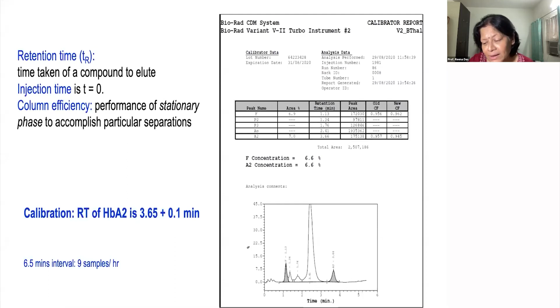After the calibrator has passed through, we have to use two controls. One is known as the low control data, and this is actually the normal control. So they call it low control data; I always say that this is normal. And what is normal over here is that the A2 percentage is in the normal range, right? And this is the total area that we were talking about, that the area has to be between 1 to 3 million, right? Then we have the high control data. So for the high control data, again, here we have a tight range of the fetal hemoglobin and the hemoglobin A2.